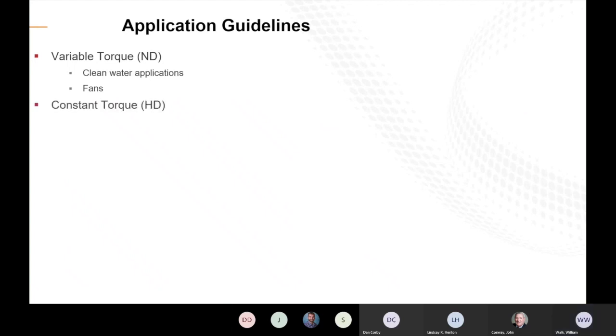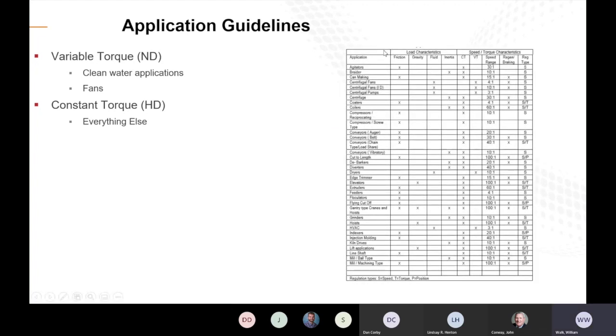So let's take a look at some application guidelines here. For your variable torque applications, it's going to be essentially everything that's clean water applications or any types of fan applications. And your constant torque or your heavy duty applications, that's going to be everything else. If you look at the matrix here, we have a list of all the types of applications. Well, maybe not all of them, but quite a few that will cover most that our customers will come in contact with. Agitators, fans. So if we look at our constant torque here for our speed characteristics, we've got all these applications here as constant torque.